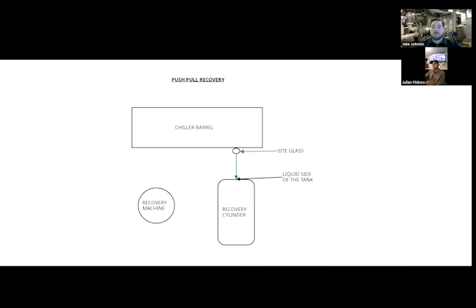That's kind of the first step. You want a sight glass there so you can verify when the liquid is out of the chiller, and that's a key point. You're going to start with liquid recovery, and then eventually switch over to vapor recovery. The sight glass is a good indicator - you can actually see the refrigerant coming out of the chiller right into the cylinder there.